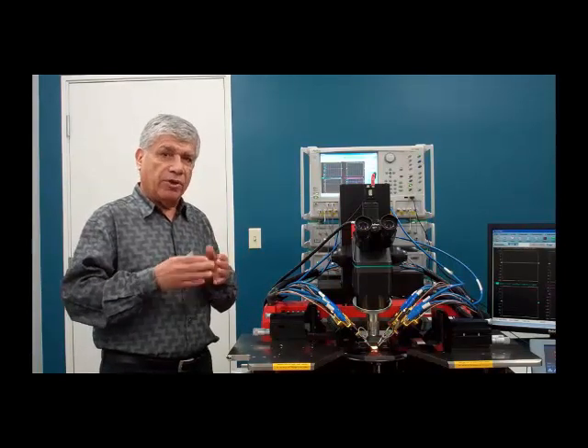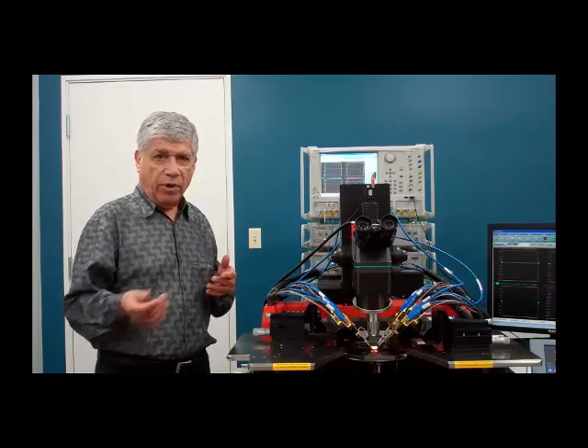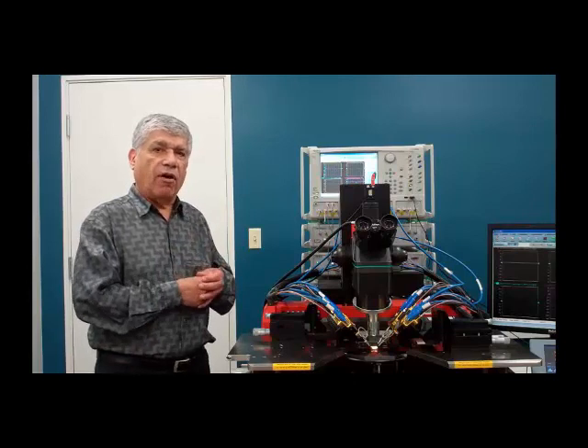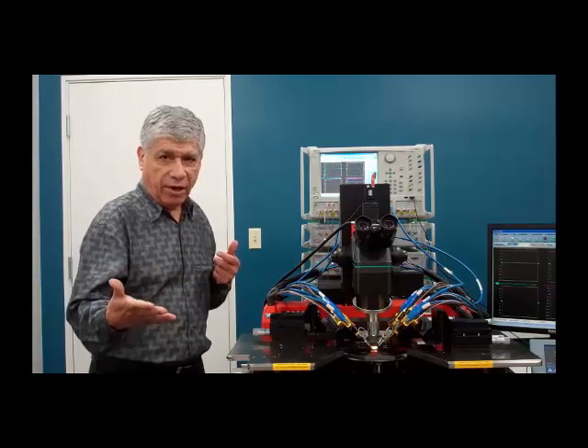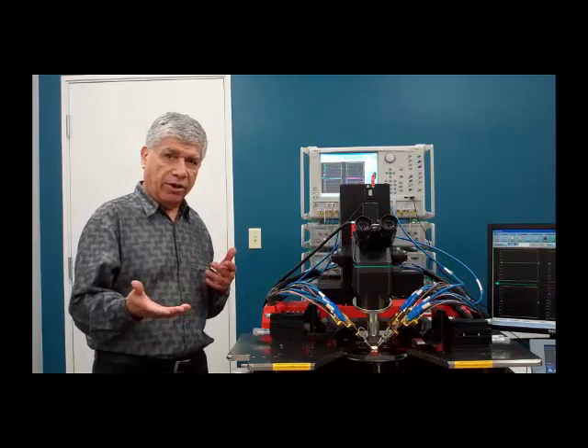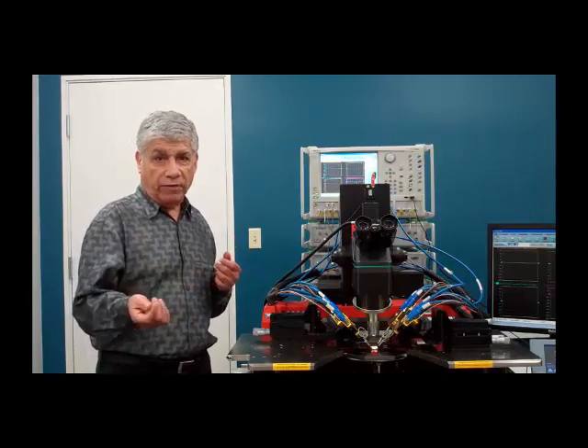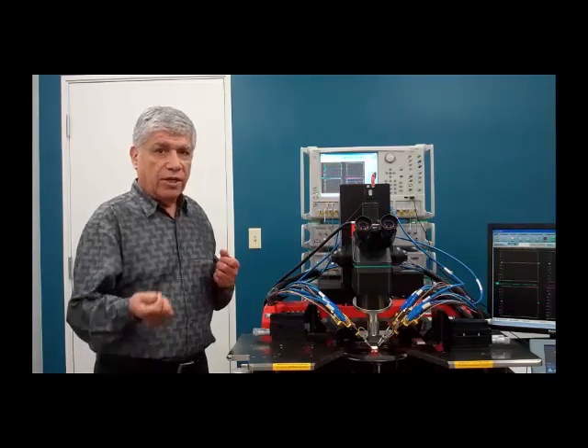Then, if we wanted to go into the millimeter wave range and do a broadband measurement, we can sweep from 70 kilohertz all the way up to the millimeter wave ranges that we cover, which is 110 gigahertz with operation to 125 gigahertz, or up to 145 gigahertz with operation up to 150 gigahertz. So adding the millimeter wave modules is what's key to the system configuration for doing a broadband sweep.